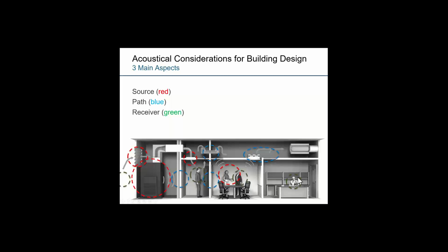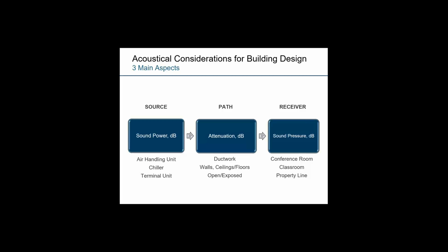And then finally, the receiver. This can be people, obviously, within a space, or even an outdoor space or a distance when there's things like property lines or bylaws that need to be met at certain hours of the day. In general, we break problems down into these 3 main aspects. When we're looking at the acoustics of a space or seeing if something is appropriate or not, we try and break things down into these 3 aspects: the source, the path, and the receiver. The source is typically, like I described earlier, the sound power, the thing that's creating the noise, often independent of environment, which would be things like air handlers or chillers or terminal units, something with a noise source contained in it. The path is a variety of different things.